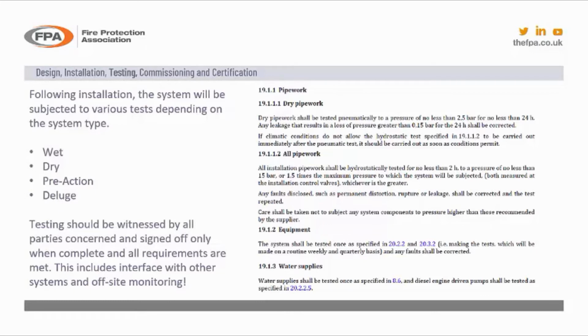So dry pipework needs to be tested for 24 hours. All wet pipework needs to be tested for a minimum of 2 hours. All the equipment shall be tested. The water supply shall be tested. Sometimes nowadays water supplies are tested at the factory and factory witnessed. So the design intent of the water supply and the performance of the water supplies are captured in the design. They then get manufactured. Clients and stakeholders get invited to do witness testing at the factory. When they go into site, they should be site tested and subject to a full test regime. Again, the testing should always be witnessed and signed off by all parties concerned.